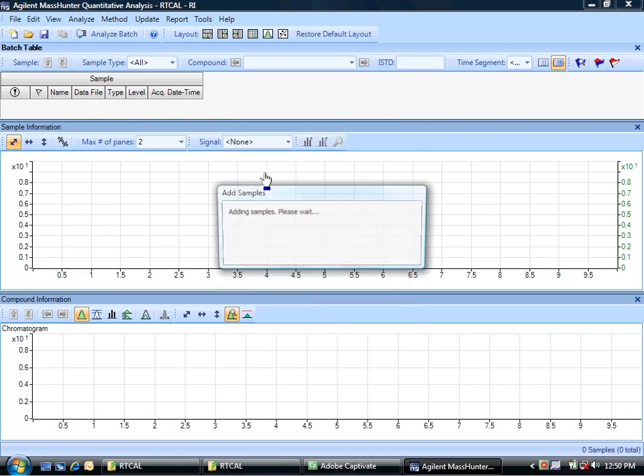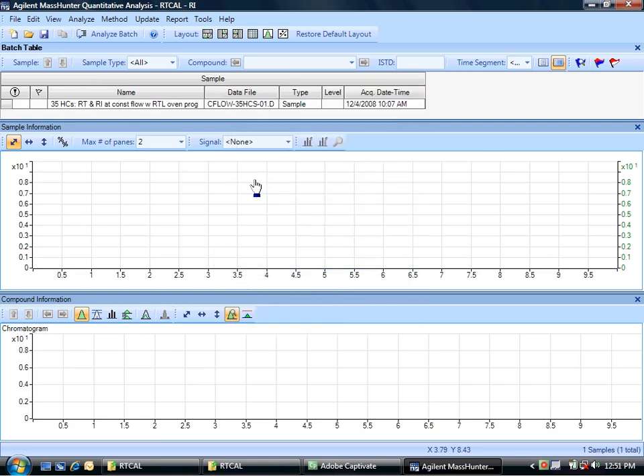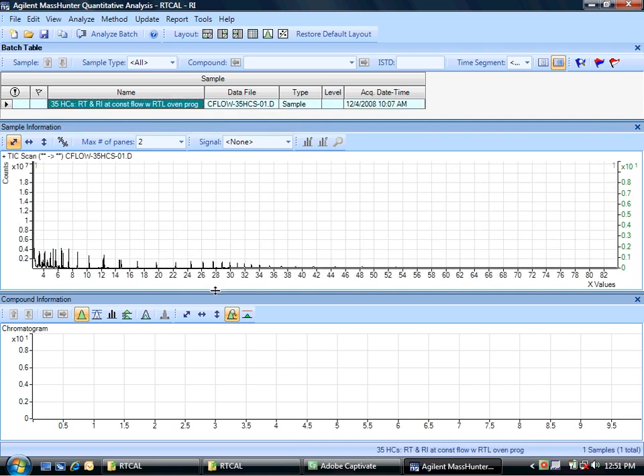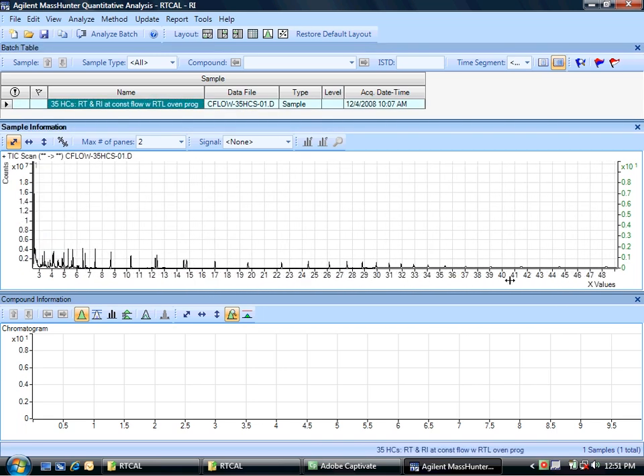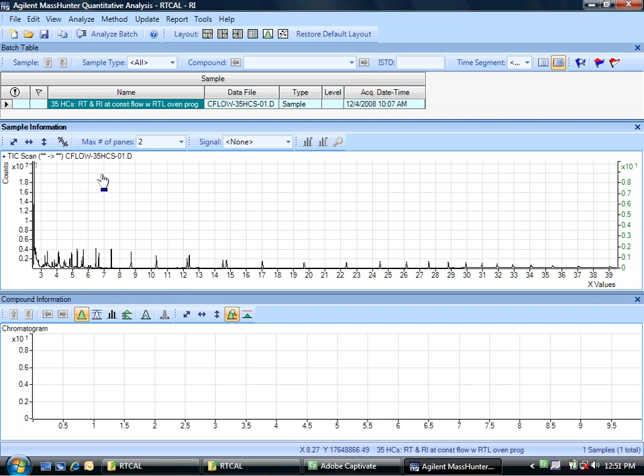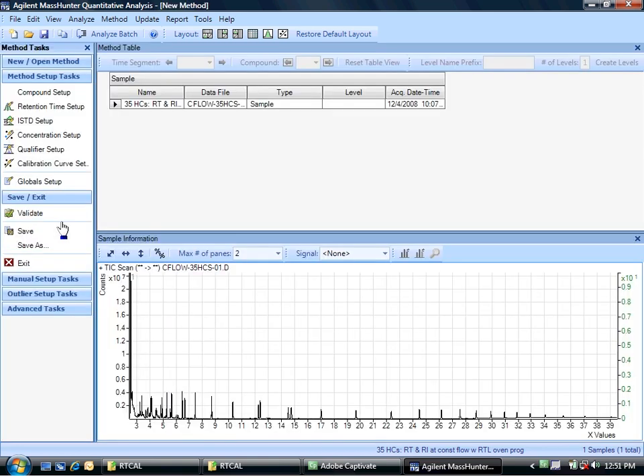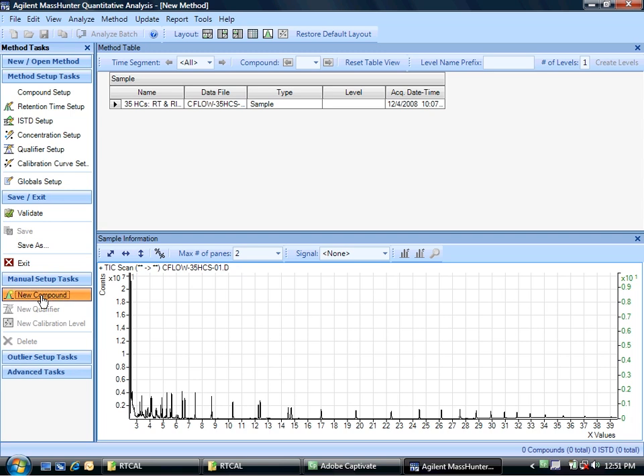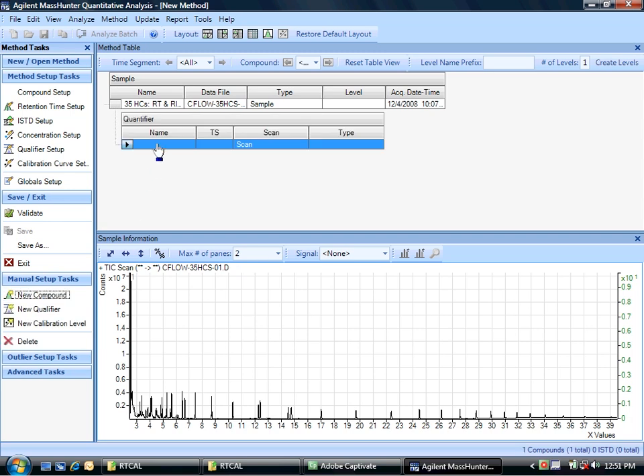I will add in that sample that I've just acquired, which is my constant flow hydrocarbon series sample. Now I have that sample and I need to go over to the method editor with that sample. I can see the hydrocarbon series here. I need to put in the compounds in the method editor so that I have a method with the compound names. There are several ways to do that; you could even do it manually by just adding the new compounds in here. Once I have that, I've got my batch and I can move to the next step.